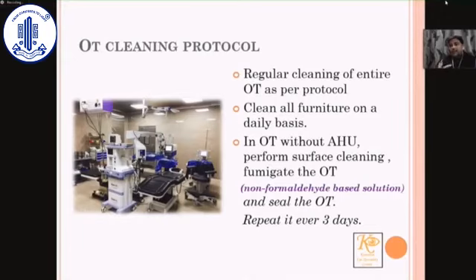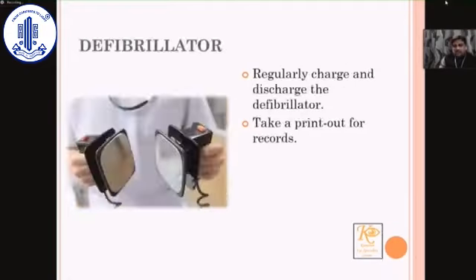There's a lot of talk about installing UV lights in operation theater, but I would not recommend it, because these UV lights in operation theater are not validated, as the luminosity at which the microorganisms are killed varies for different organisms. The UVC lights, which are usually installed on the walls, seldom reach a lethal level on your tables, not to mention the floor. But UV lights work well in a very closed enclosure like your CSSD area or inside an AHU. Installing them in your theater is not actually validated.